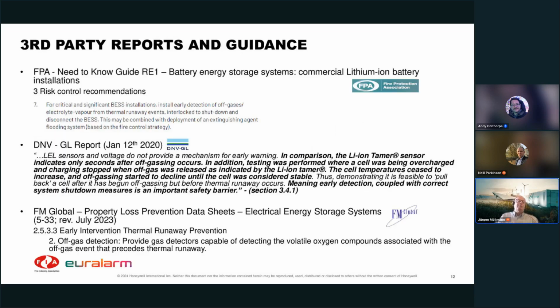Third-party report and guidance: I just mentioned the FPA Need to Know Guide RE1, battery energy storage systems. Their risk control recommendation also looks at electrolyte vapor detection. DNV Global did a test in 2020, and they mentioned the Li-ion Tamer as the only technology that can detect the off-gas event. Also, FM Global mentioned early intervention thermal runaway prevention, in the July 2023 revision, where they added off-gas detection as a preferred solution for detecting the electrolyte and preventing thermal runaway.